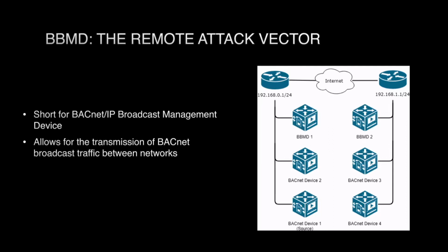On the diagram on the right, you can see 2 such BACnet networks, each having a BBMD. The way this works is that broadcast traffic intended for a foreign network is first sent to the source network's BBMD. This sends it to the destination network's BBMD, and its job is to rebroadcast it on the destination network.